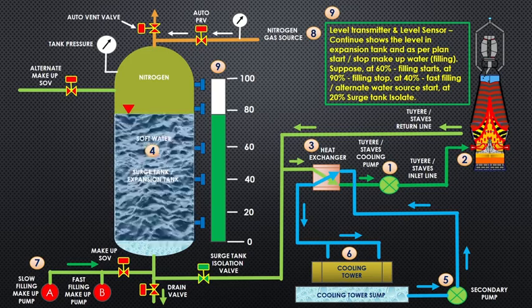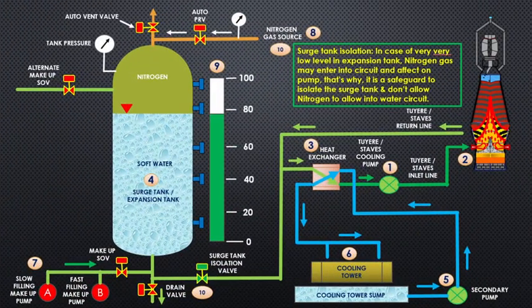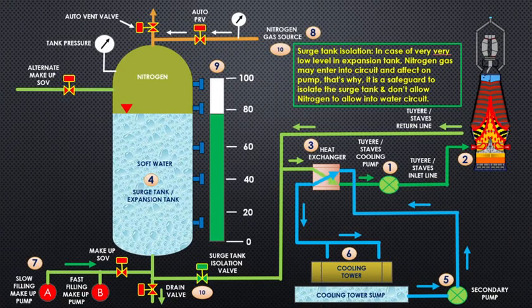Surge tank isolation: in case of very low level in expansion tank, nitrogen gas may enter into circuit and affect the pump. That's why it is a safeguard to isolate the surge tank and don't allow nitrogen into water circuit.